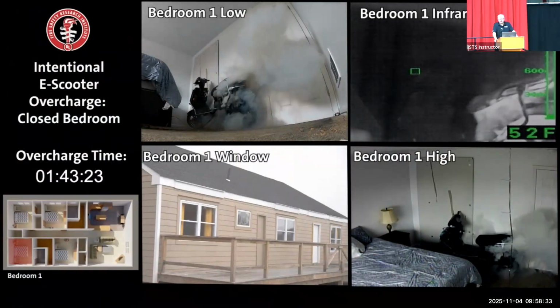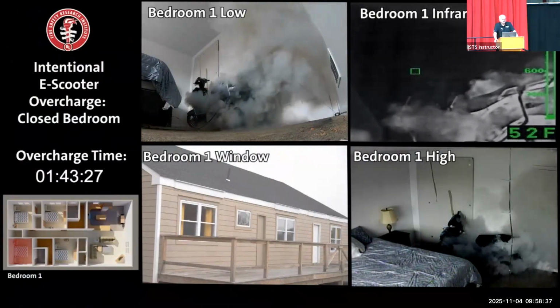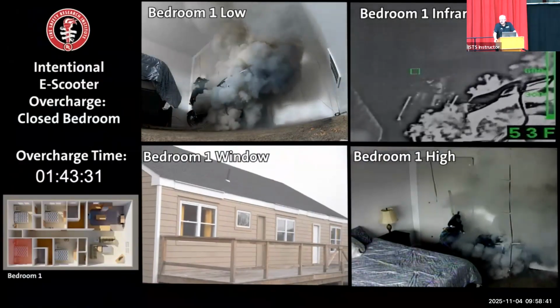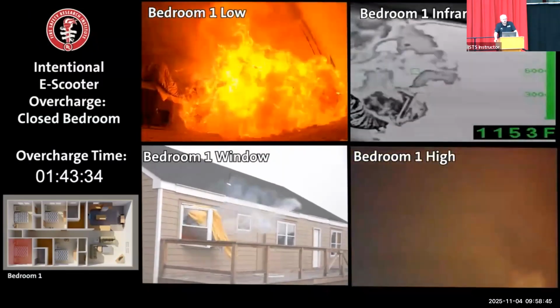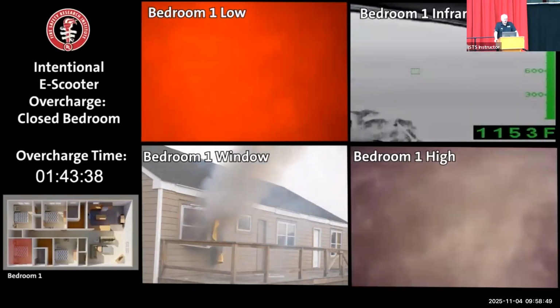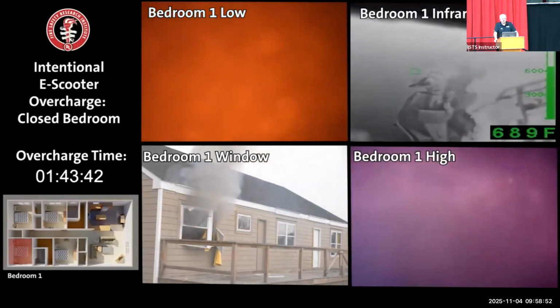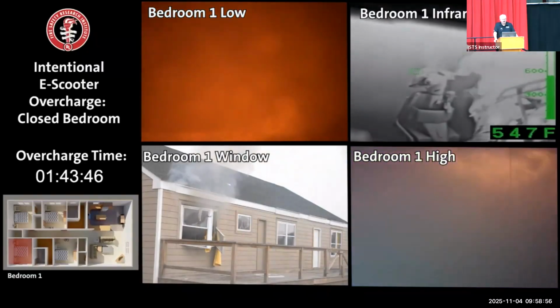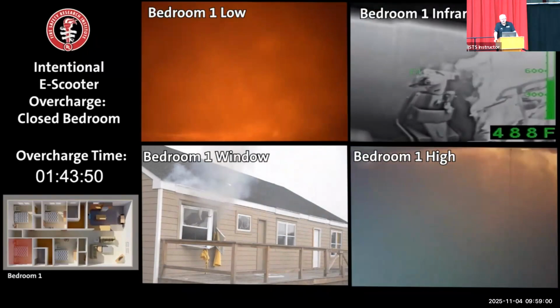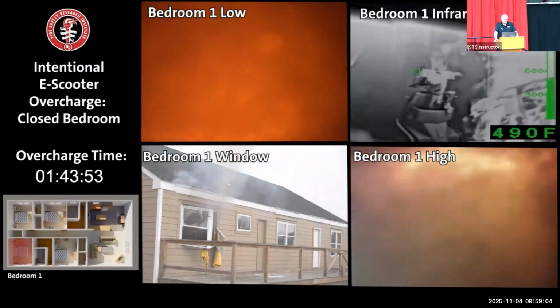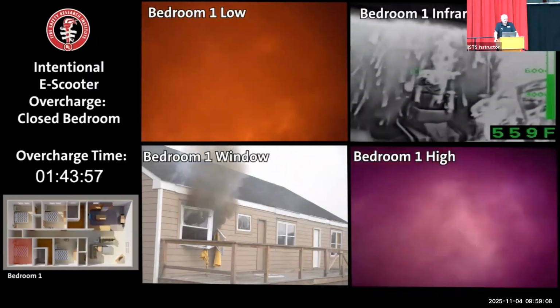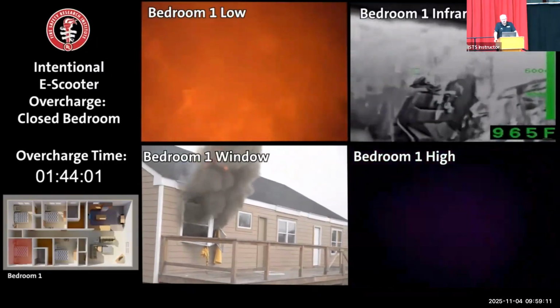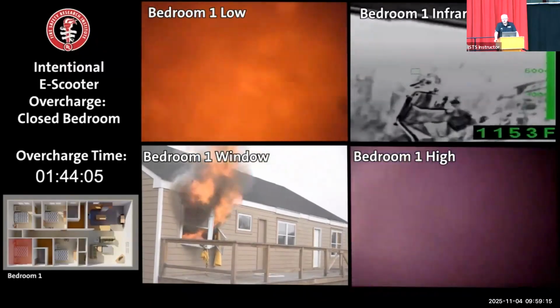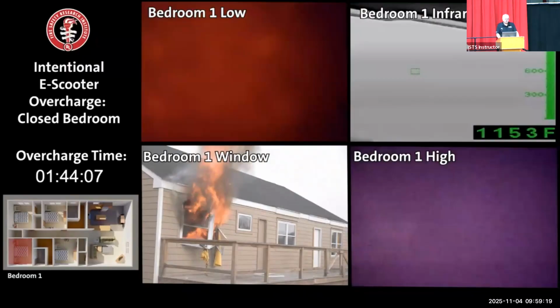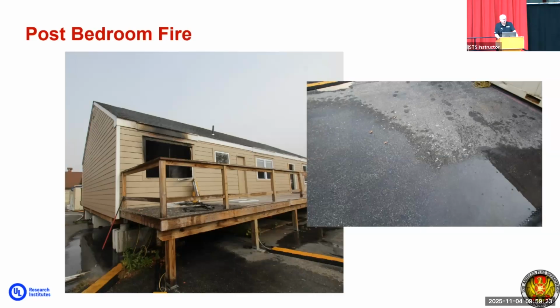So we see the smoke, additional smoke as additional cells vent. We see some mixtures of sort of white, gray, black, and then the ignition. So we have an overpressure. The overpressure blew glass out of the window. The hollow core door, even though part of the interior finish was burning away, held and isolated the bedroom from the rest of the house. So the conditions in the hallway, while not pristine, were very low temperature with just a relatively small amount of smoke leaking. However, that pressure, this house had a central heating and air conditioning unit, so that pressure then drove smoke in through that unit. So what we see here is the glass blowing out of the window, 30 feet away from our test prop.